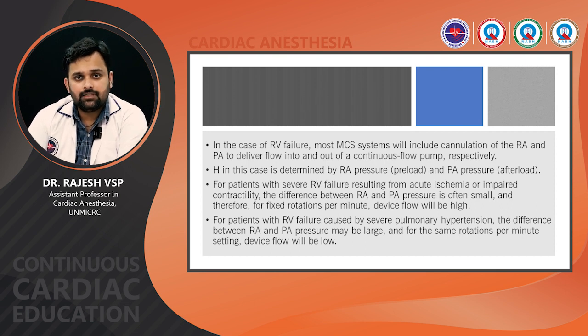In case of RV failure, most MCS systems will include cannulation of the RA and PA to deliver flow into and out of a continuous flow pump respectively. The pressure gradient, that is H, in this case is determined by RA pressure, that is preload, and PA pressure, which denotes afterload. For patients with severe RV failure resulting from acute ischemia or impaired contractility, the difference between RA and PA pressure is often small, and therefore for fixed rotations per minute, device flow will be high. For patients with RV failure caused by severe pulmonary hypertension, the difference between RA and PA pressure may be large, and for the same rotations per minute settings, device flow will be low.